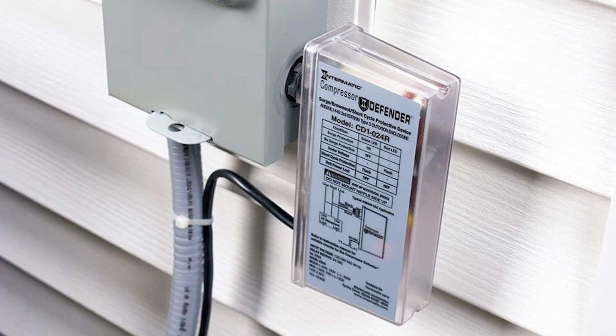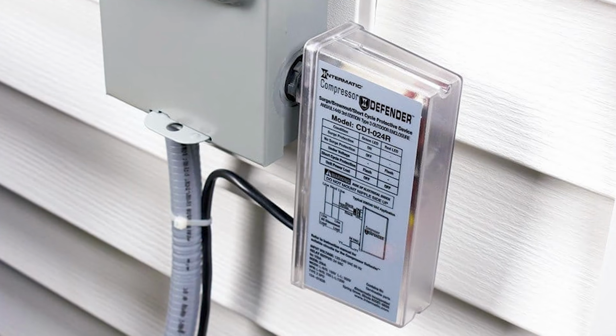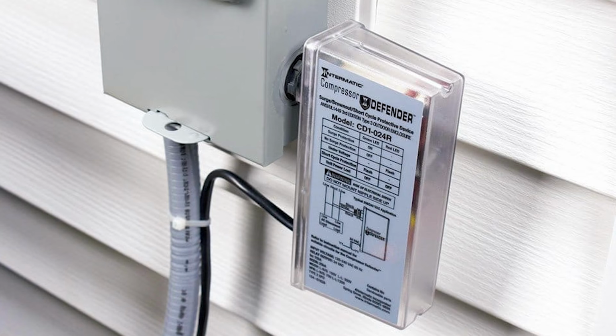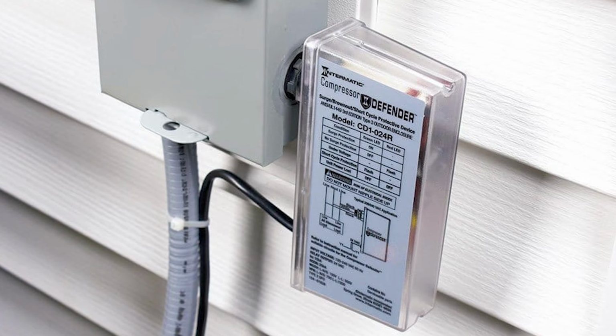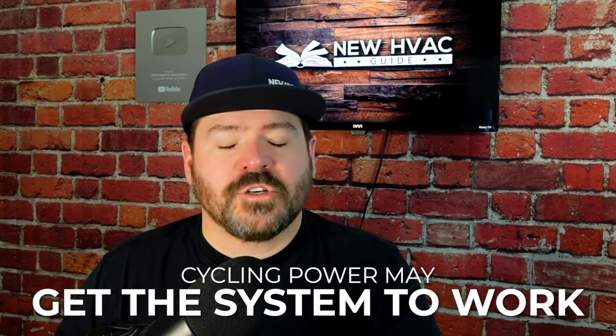Other issues might be, say, a surge - you had a power surge on that system and the surge protector has turned the system off. If you've got some sort of protection wired in series with the high voltage... the cheap surge protectors are wired parallel and don't actually turn the system off, they're just grounding a lot of the problems from a surge, for example. But if you have one of the products that's wired in series and it actually can kill power to the system because there was an issue, cycling power may actually get that system to work again. So I'm just throwing a couple scenarios out there.